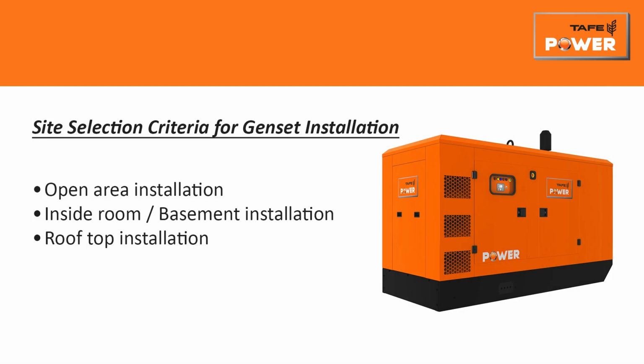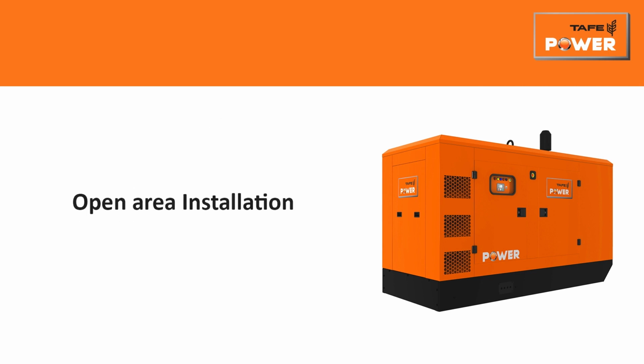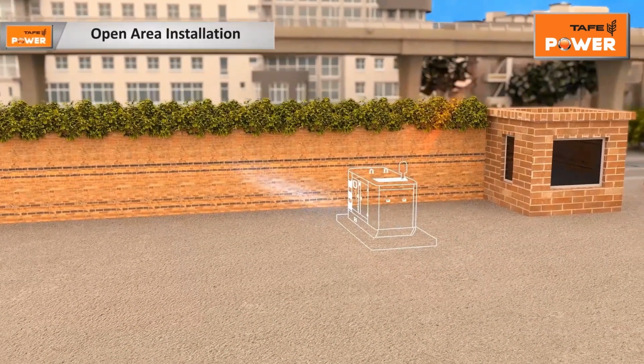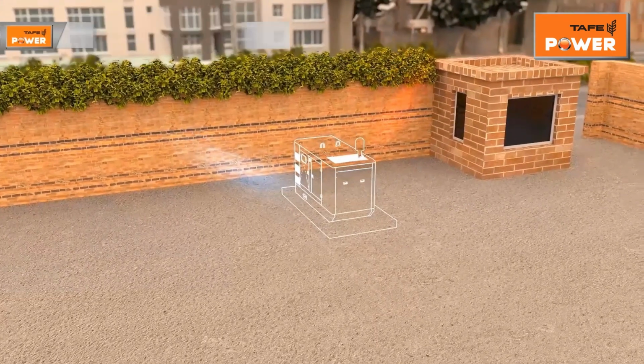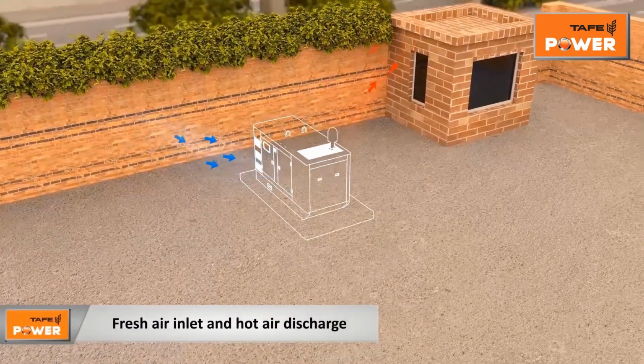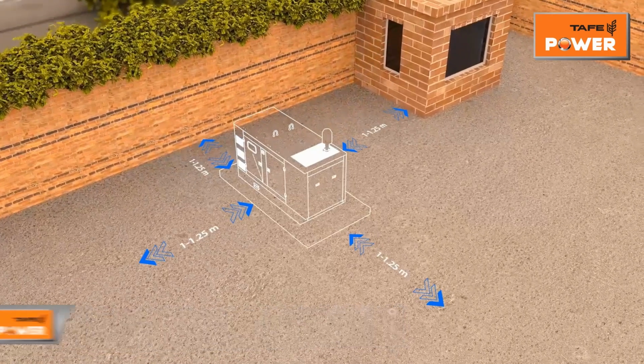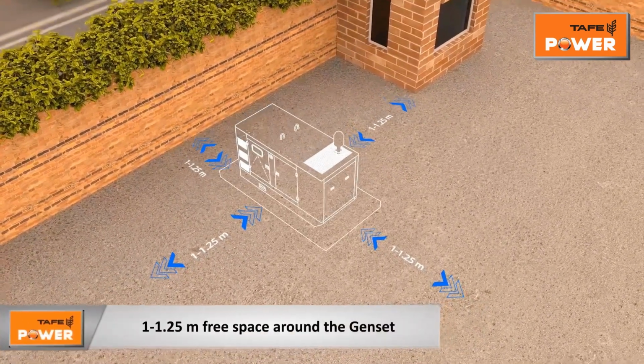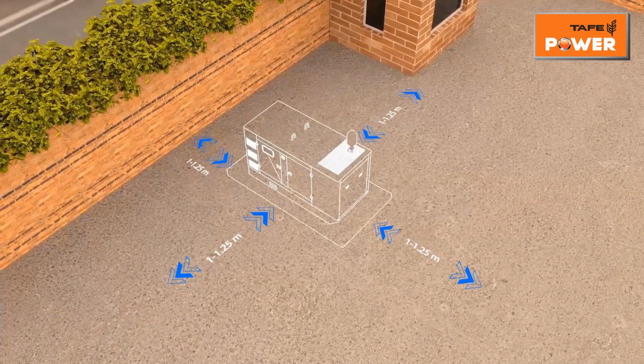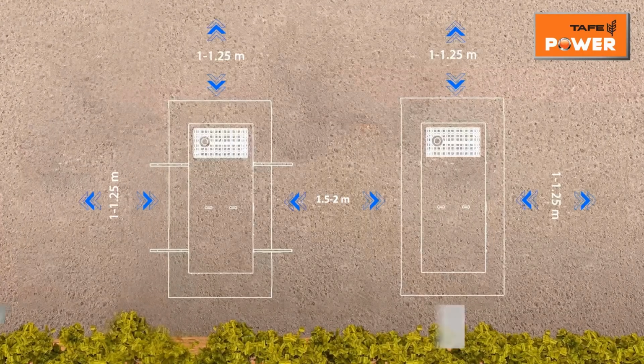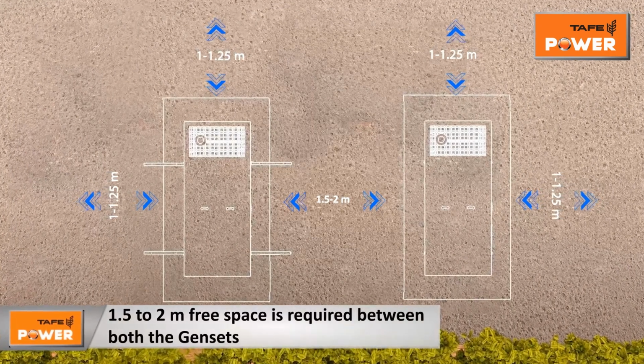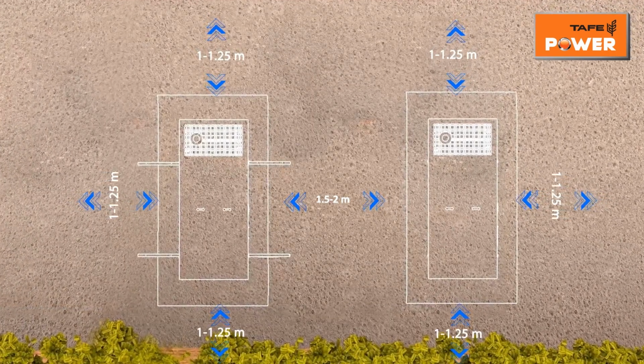Gensets can be placed preferably in open areas on RCC or PCC foundation, inside room or basement of a building with proper ventilation arrangement, or on rooftop. Open area installation. TAFE power gensets have provisions of cross airflow with cutouts for fresh air inlet and hot air discharge. Ensure free space of 1 to 1.25 meter around the genset and free flow of air. For multiple genset installation, minimum 1.5 to 2 meter free space is required between both the gensets.